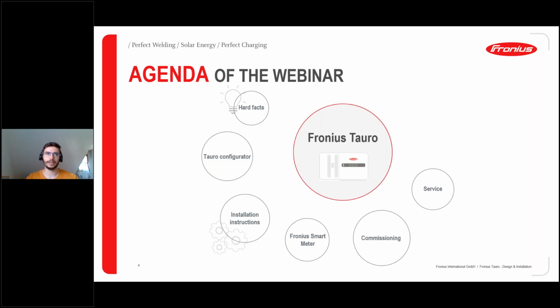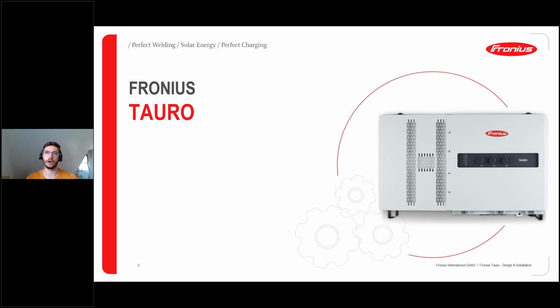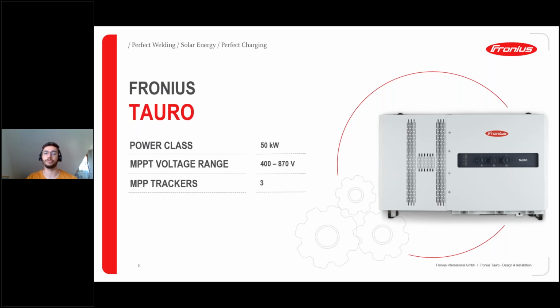We will start directly with the hard facts of the Fronius Tauro. As you may have already heard, we will have two Tauro devices, the Fronius Tauro and the Tauro ECO. The Fronius Tauro comes in the power class 50 kilowatt, with an MPP voltage range of 400 to 870 volts on the DC side, with 3 MPP trackers in total. The input currents for those 3 MPP trackers are 36 amps on the first two and 72 amps on the third one.